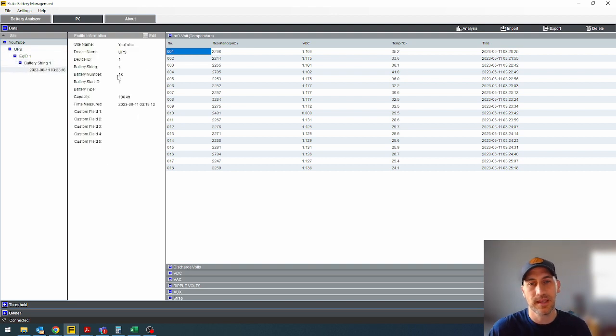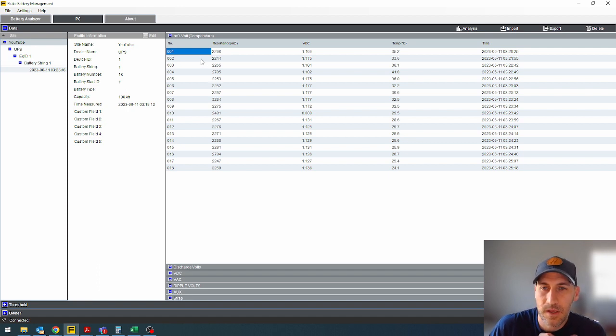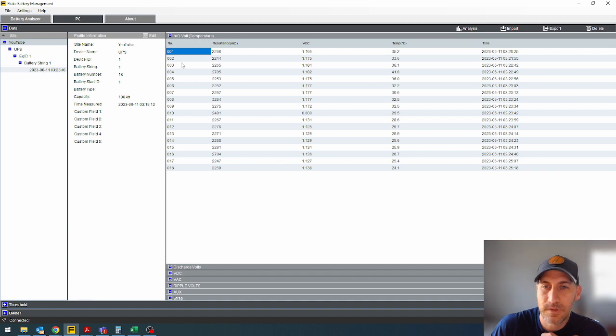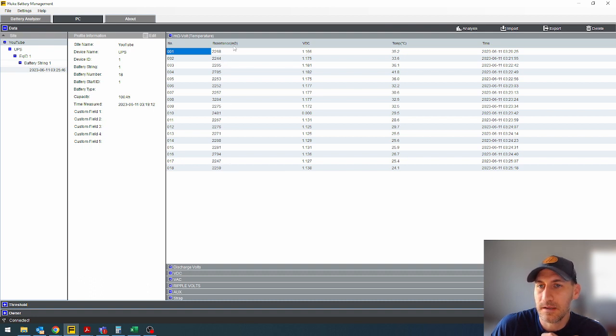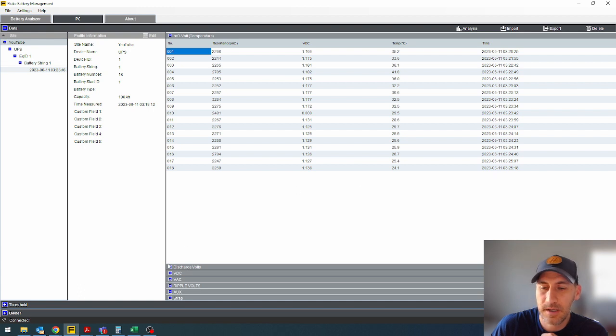Over here we have the impedance reading. So we've got all our 18 batteries that we tested, the resistance or impedance that we got in milliohms. You have DC voltage, temperature in Celsius, and then time and date stamped.